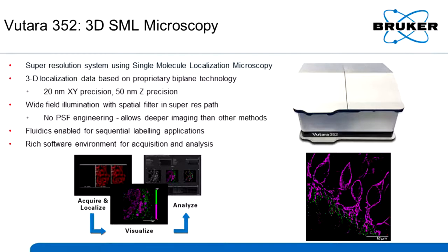The system gives us 20 nanometer X-Y precision, and in every experiment you also get 50 nanometer Z precision. It uses wide field illumination with a spatial filter in the super-res path, but there's no point spread function engineering involved, which means we can image deeper than other single molecule systems. We have fluidics enabled — the fluidic system is integrated into the hardware — so we can do sequential labeling applications. And we have a rich software environment for acquisition and data analysis built into the system.